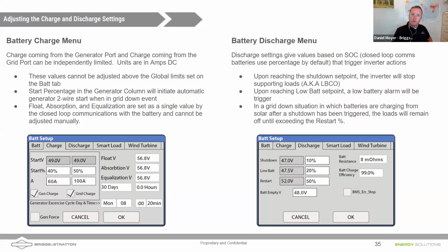Yep. Going over to the discharge tab, we're still in the bat setup tab, and discharge, right? I see three values there, right, Andrew? I see low bat, which would kind of occur first. That's when the batteries are getting low. There's no solar, there's no grid, there's no generator. When the batteries get to 20%, you're going to get an alarm, right? The inverters are going to start beeping at you. You might get an alarm on your app too. If they don't do anything, they don't shut off loads, the homeowner, at 10%, the loads to the house will get shut off. That's the shut off value.